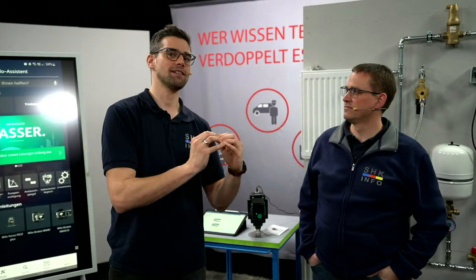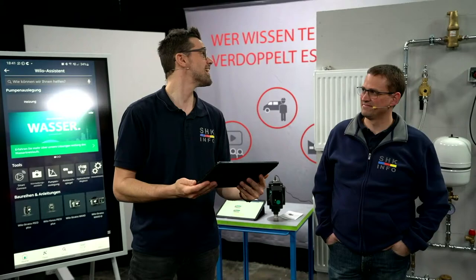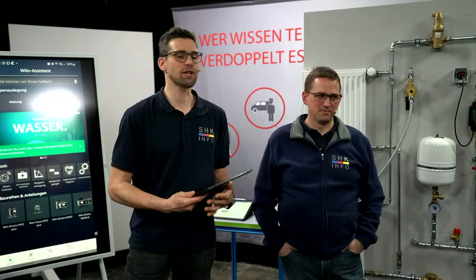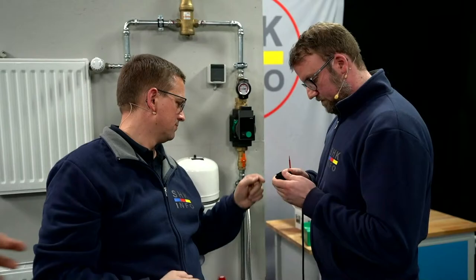Da kam gerade noch etwas im Chat. Einer hat noch das mit der Luft gehört, der Mikroblasenabscheider lief. Hat die einen Verpolschutz? Im Stecker drin sieht man sehr deutlich L, N und PE. Tatsächlich – wenn man jetzt N und L vertauscht, ist das nicht ganz so tragisch. Aber wenn ich den L auf die Erde lege, da nützt auch der beste Verpolschutz nicht. Von daher sollte man da auf jeden Fall darauf achten, dass man die richtigen Drähte auf die richtigen Anschlüsse setzt.